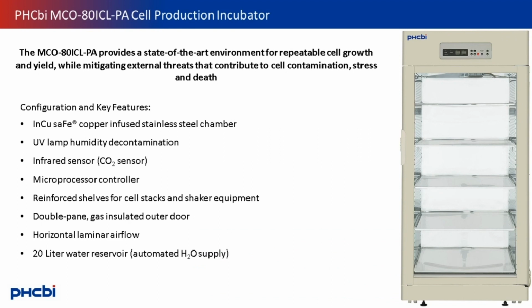Our MCO 80ICL cell production incubator is the perfect incubator for a lab that is looking to scale up their cell culture, providing a state-of-the-art environment for repeatable cell growth and yield, while mitigating the external threats that contribute to cell contamination, stress, and even death. The IncuSafe copper-infused alloy passively mitigates contamination while remaining corrosion resistant and easy to clean. The ultraviolet lamp actively decontaminates the humidity source safely behind a plenum wall. Infrared sensors measure atmospheric CO2 directly for uniform, precise CO2 control even after door openings.